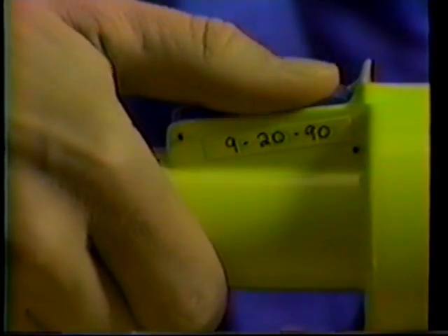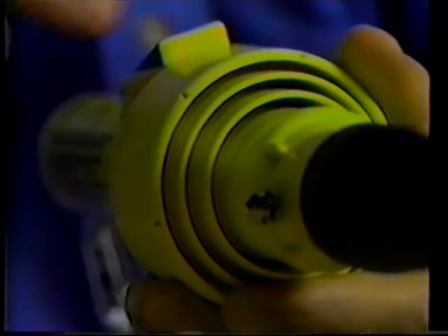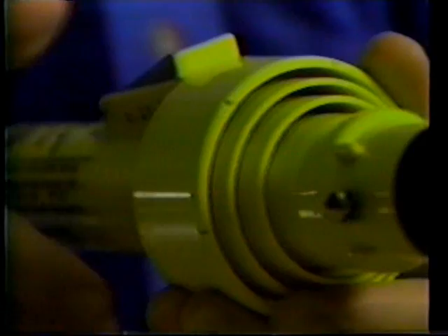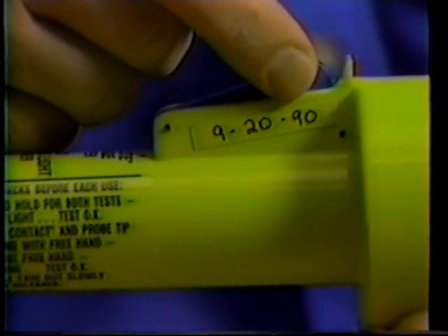In the middle of the unit is the flash guard, with 3 concentric circles. A non-conductive colored label is applied to the side of the switch and lists the date the test set was last electrically tested with simulated high voltage. A label containing operating and safety instructions is attached to the handle of the unit.